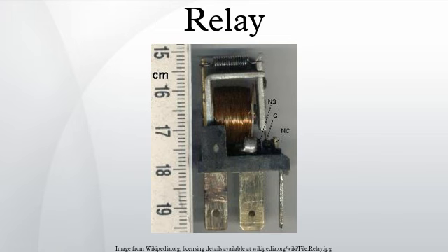Buchholz relay. A Buchholz relay is a safety device sensing the accumulation of gas in large oil-filled transformers, which will alarm on slow accumulation of gas or shut down the transformer if gas is produced rapidly in the transformer oil. Forced guided contacts relay. A forced guided contacts relay has relay contacts that are mechanically linked together, so that when the relay coil is energized or de-energized, all of the linked contacts move together.